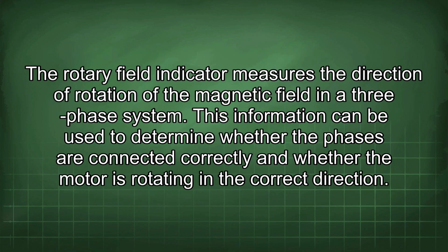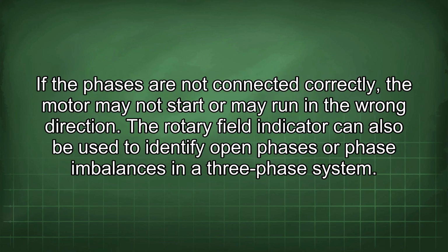The rotary field indicator measures the direction of rotation of the magnetic field in a three-phase system. This information can be used to determine whether the phases are connected correctly and whether the motor is rotating in the correct direction. If the phases are not connected correctly, the motor may not start or may run in the wrong direction. The rotary field indicator can also be used to identify open phases or phase imbalances in a three-phase system.